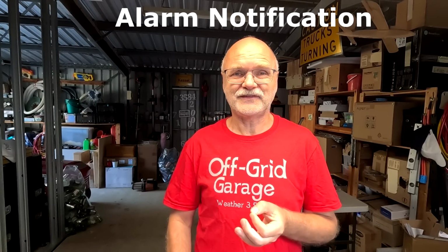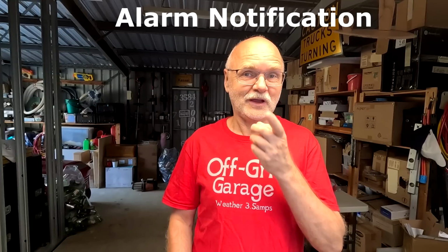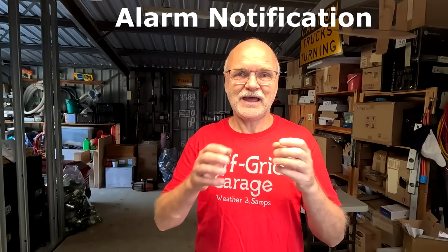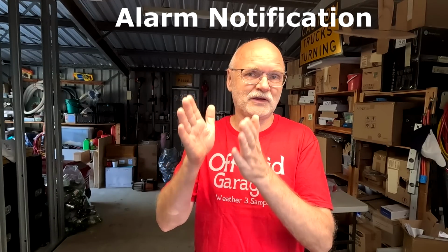So the next thing they have fixed is the alarm notification. As you may remember from my previous testing, when we have several batteries in parallel and one of them has, for example, an over temperature protection, this one battery turns off, but all the other batteries keep charging. It reports this status to the master BMS, and the master BMS requests a reduced charging current because we are one battery short. Yeah, this was all working fine, but the complaint was there is no actual notification to the user that there is an issue with one of the batteries. Unless you look on the front panel and you can see the red light flashing. But this light is so tiny nobody actually notices that.